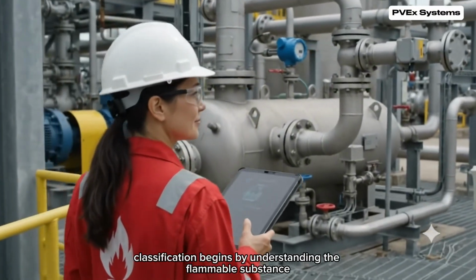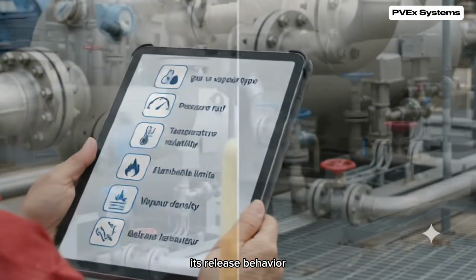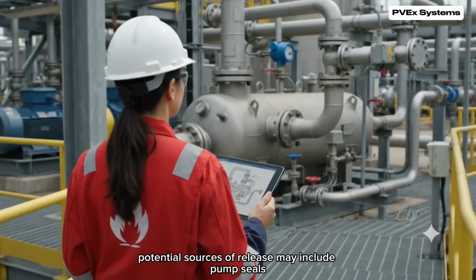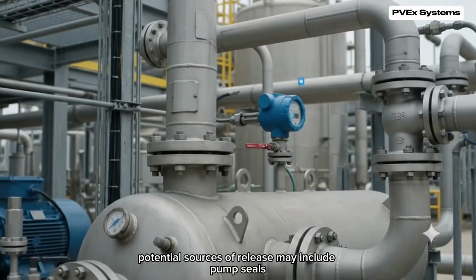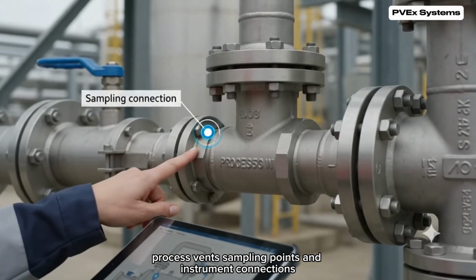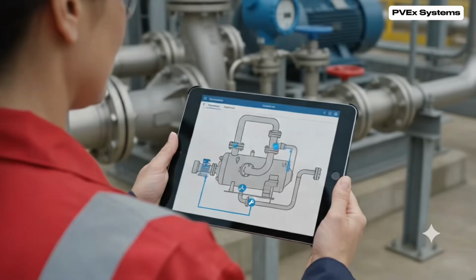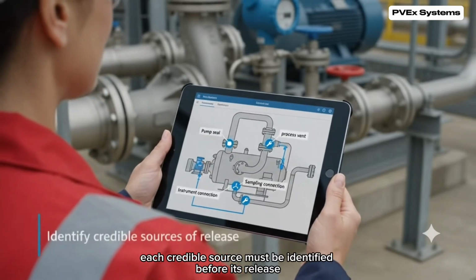Classification begins by understanding the flammable substance, its release behavior, and the process conditions that influence evaporation, dispersion, and accumulation. Potential sources of release may include pump seals, process vents, sampling points, and instrument connections. Each credible source must be identified before its release.